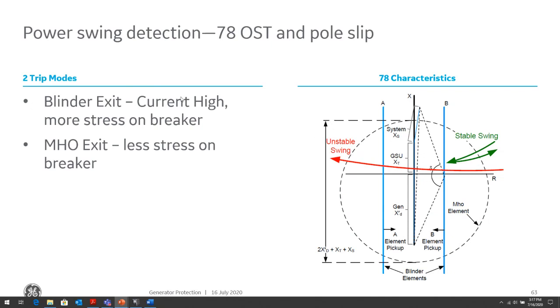Our strategies for tripping are during blinder exit or Mho exit. When we talk about blinder exit, we're going to trip when the unstable swing exits the left blinder, the blinder that's in the negative region. The issue with that is that the power swing is still very close to the generator at that point, so we can see high currents, and if we call upon the breaker to open, it can stress the breaker.